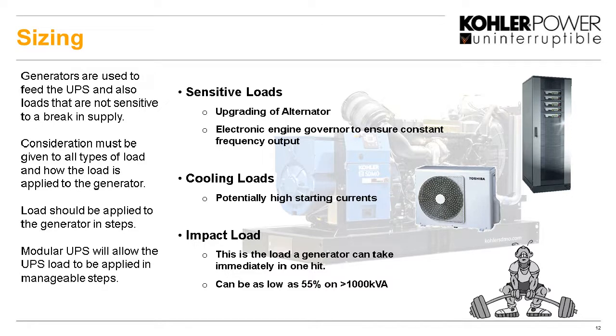Okay, so on big sets that can be less, and we also see that on modern sets it's actually declining. So we have to make sure we put the load onto the generator as stepped as well as we can, and this is where we work very well between our modular UPS and generators, because we can step in the load very managed and very small and keep that generator running at the right frequency and voltage.